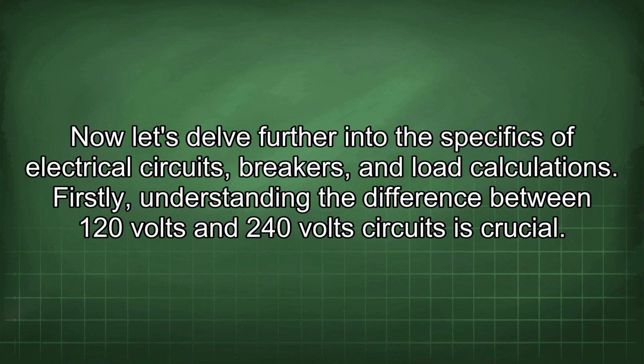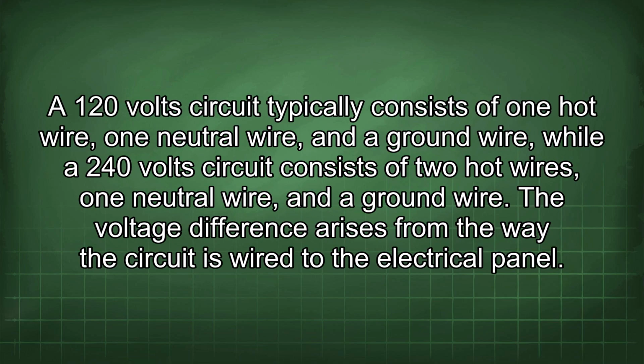Firstly, understanding the difference between 120-volt and 240-volt circuits is crucial. A 120-volt circuit typically consists of one hot wire, one neutral wire, and a ground wire, while a 240-volt circuit consists of two hot wires, one neutral wire, and a ground wire. The voltage difference arises from the way the circuit is wired to the electrical panel.